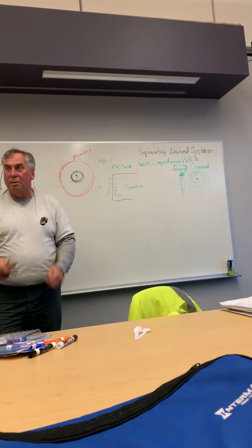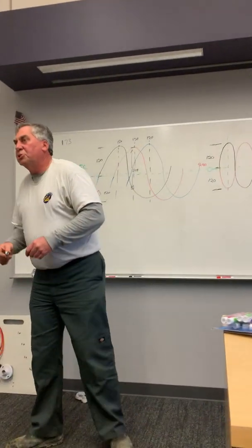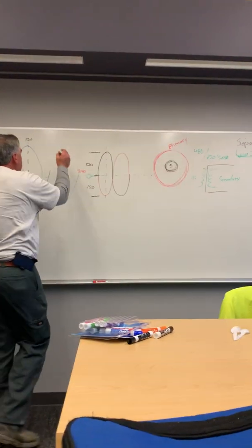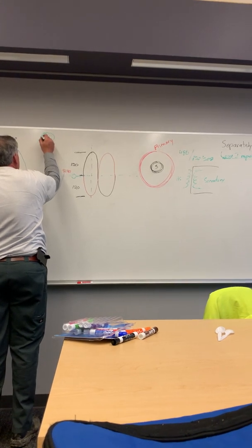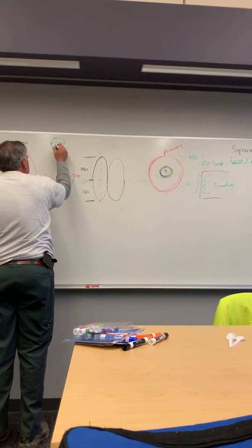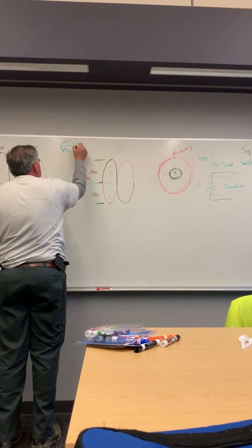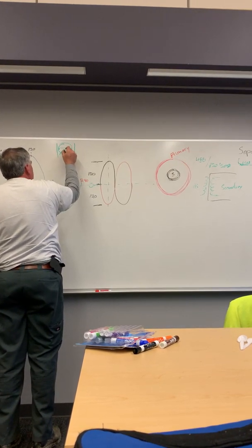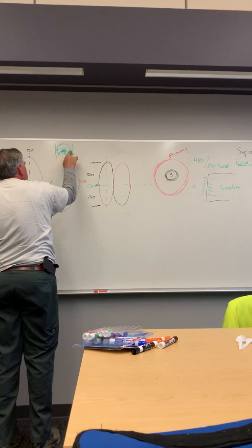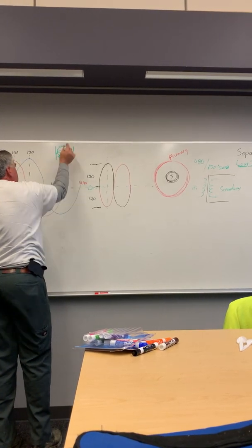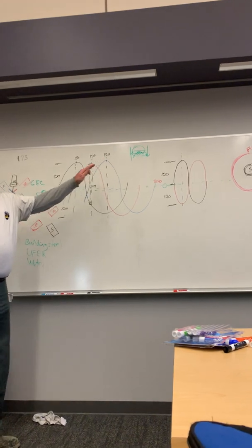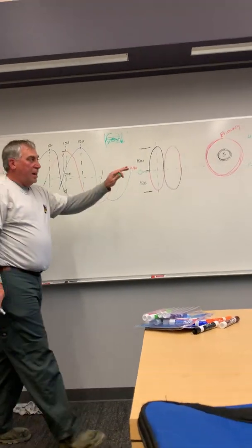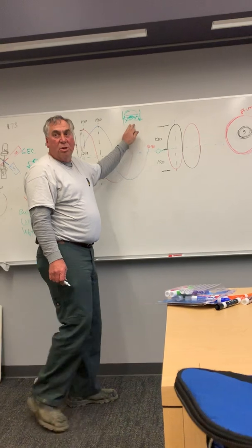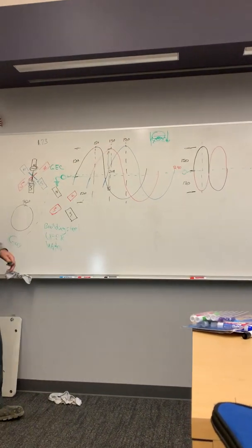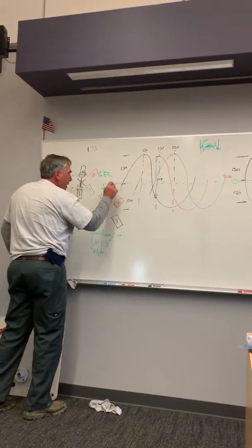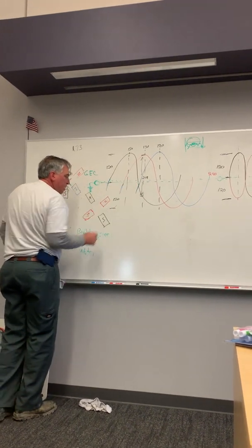Are you talking about that grounding bushing? A grounding hub, yeah. It's just a brass grounding hub with two screws in it. The wire's right here, and it kind of grabs it like that. Terrible art, I'm sure somebody could draw a lot better than I can. But when they talk about a low impedance path to ground, these are the little tricks we use to keep it as tight as we can, and we'll get back to that. So now we're talking about this low impedance path to ground.